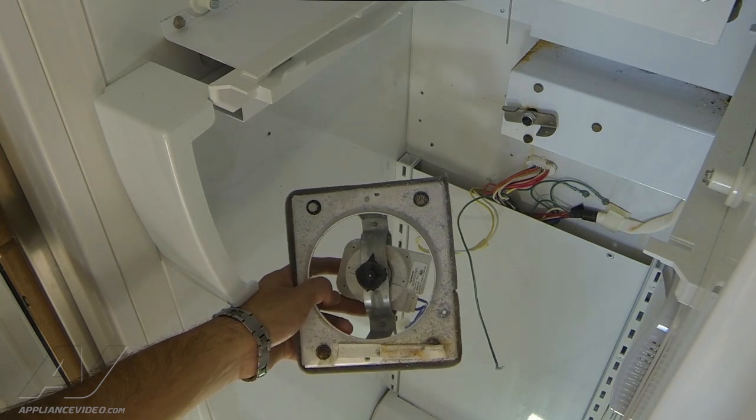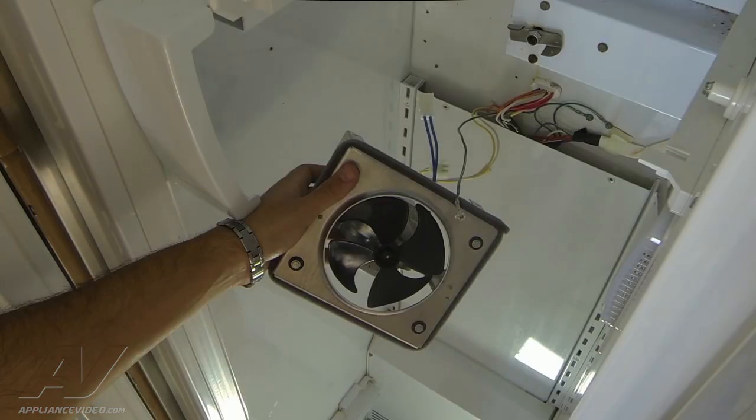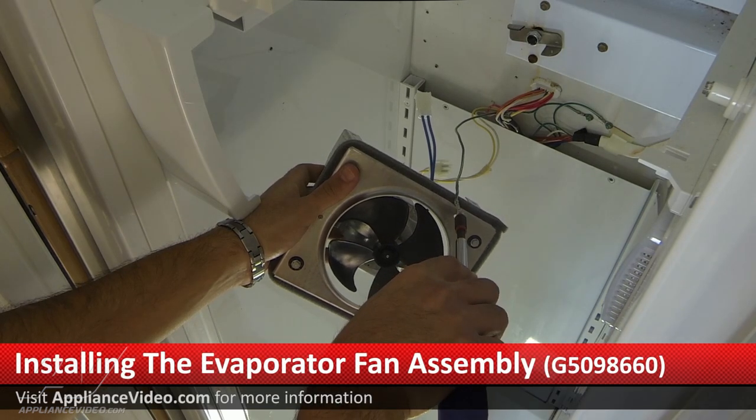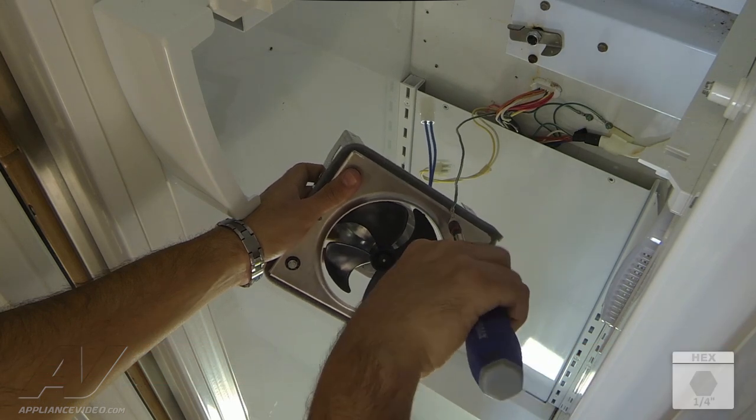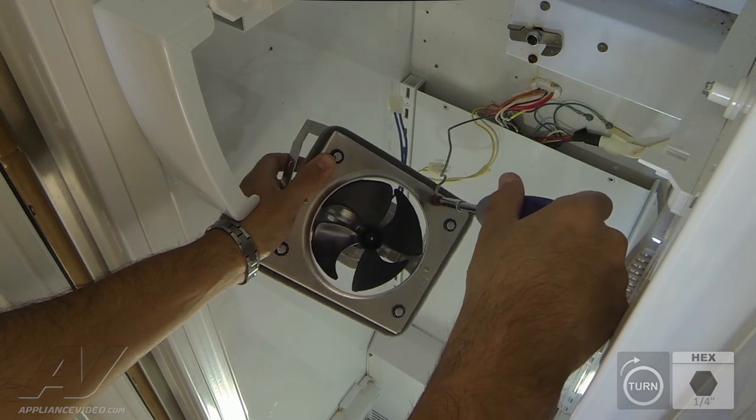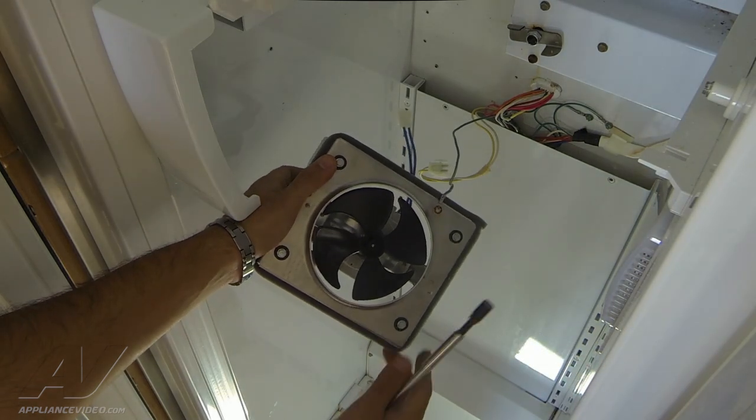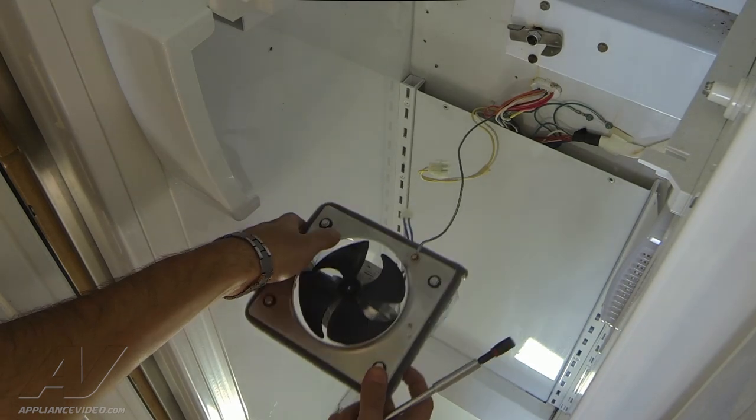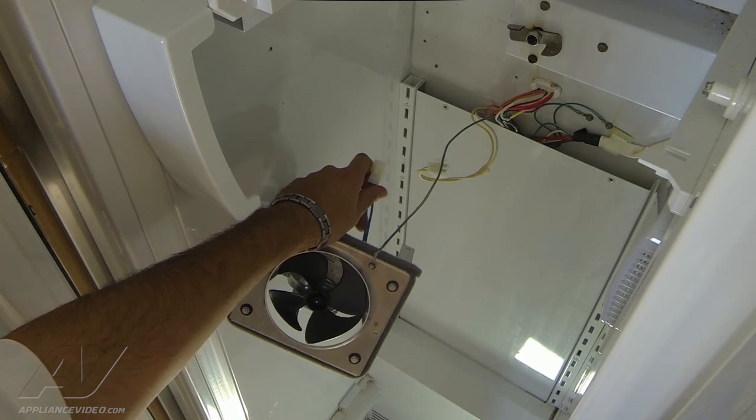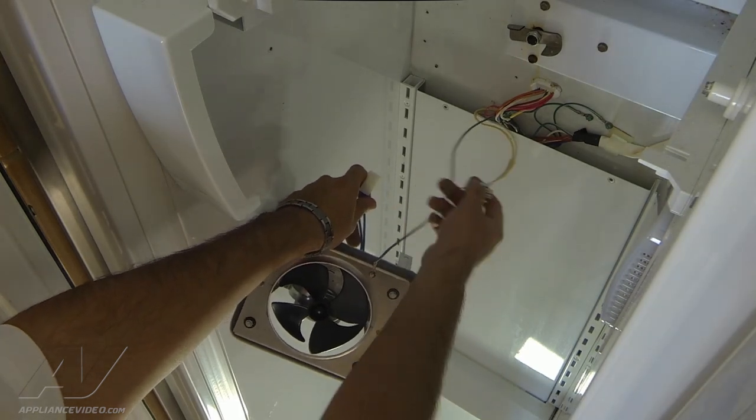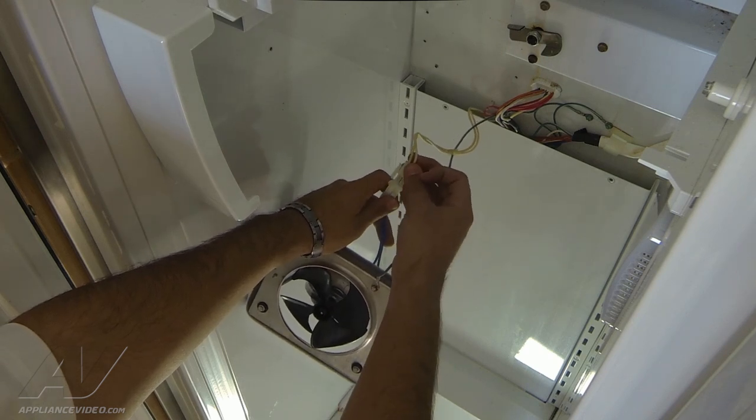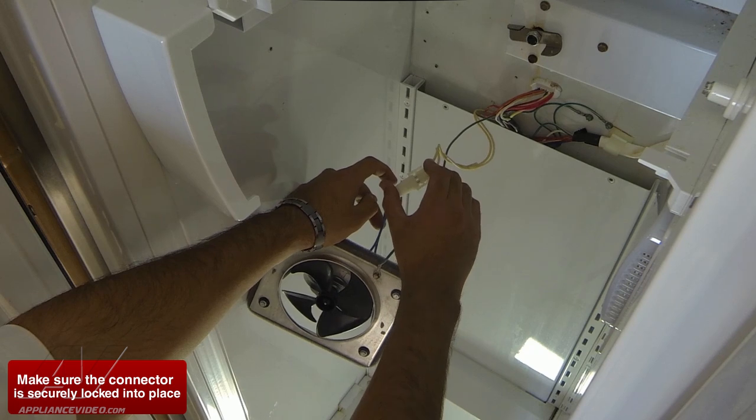Now we're ready to install the new evaporator fan motor assembly. We're going to install the ground strap to the new fan motor assembly. It goes in the same exact position as the old one. Once the ground strap has been installed, we can reattach the wires that go to the fan motor to the connector. It's keyed to go on one way only, so you find the correct position and just push the clips together.